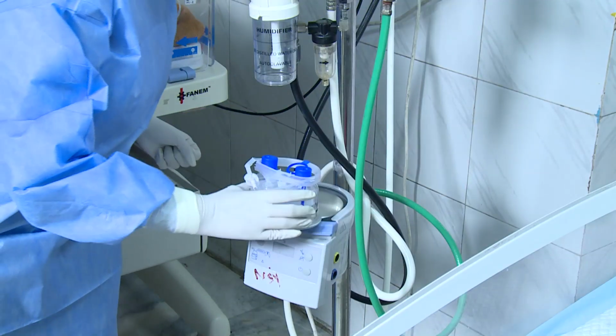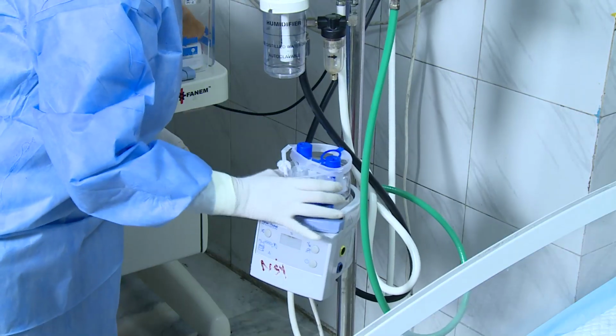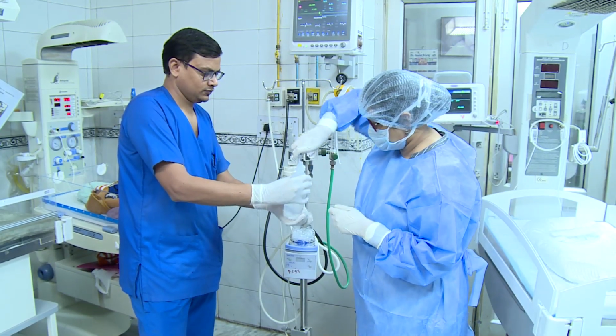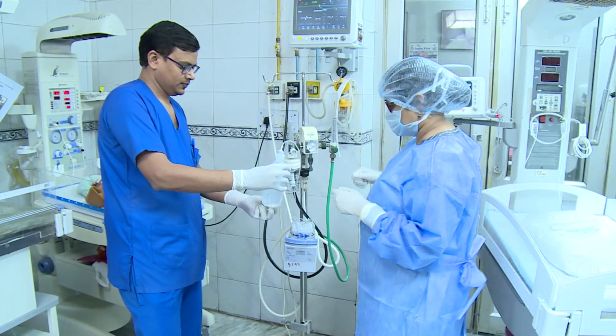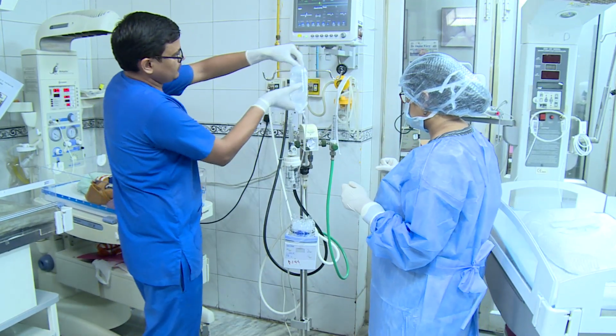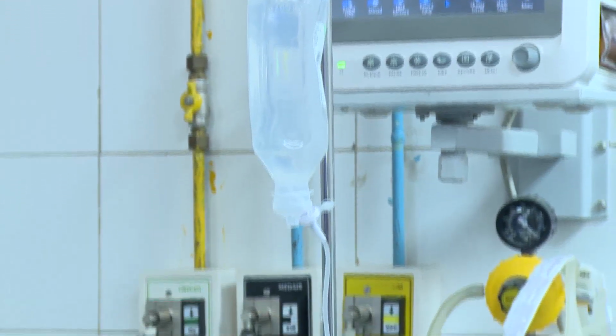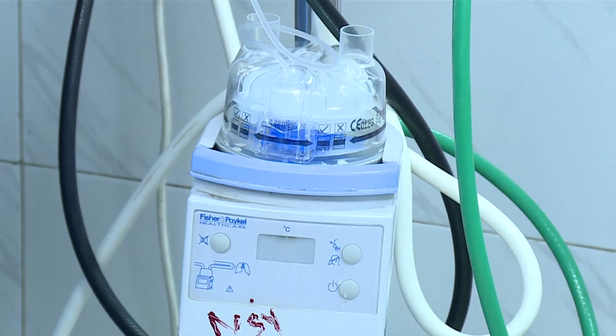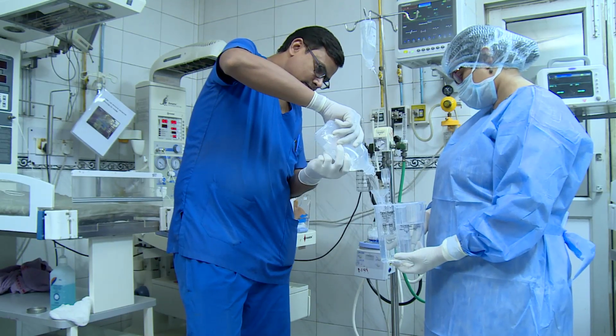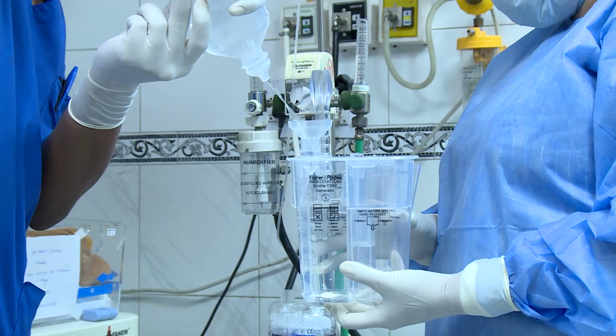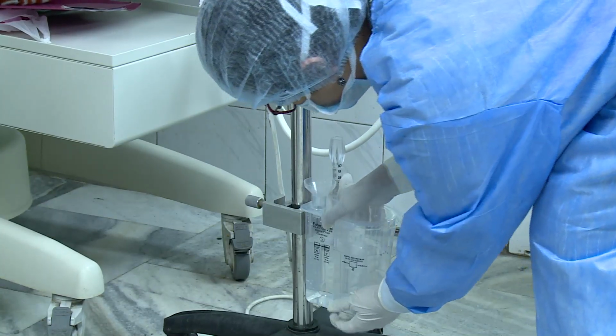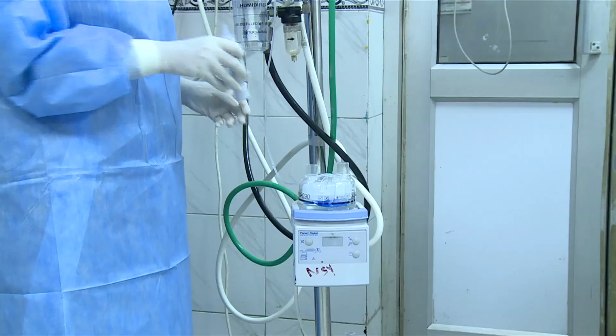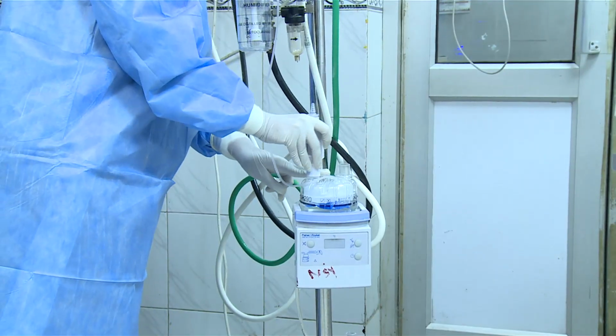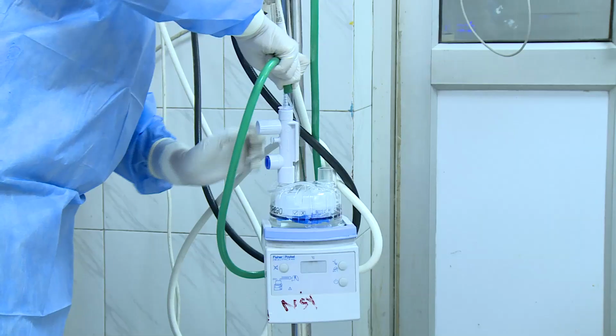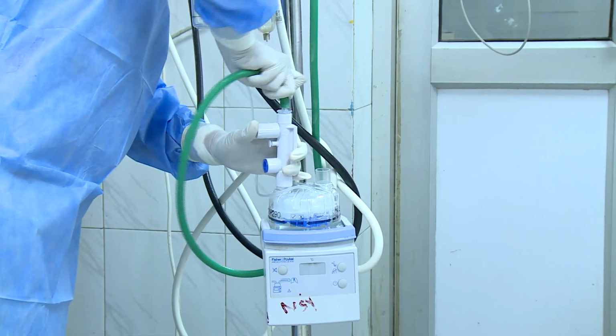and fix the water chamber onto the servo humidifier. Fill the water chamber with distilled water so that the oxygen delivered is humidified and warm. Use the autofill method for filling the water chamber with distilled water. Fill the bubble chamber with distilled water till the marking and fix it in the slot available in the CPAP machine stand. Connect the safety device between the water chamber and the flow meter using the green colored tubing.